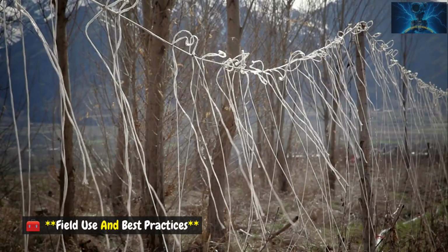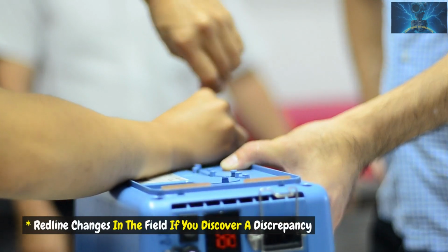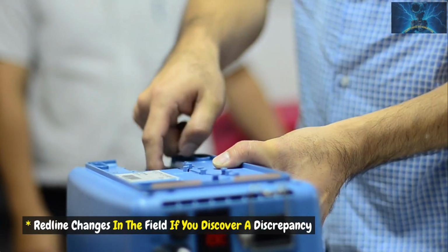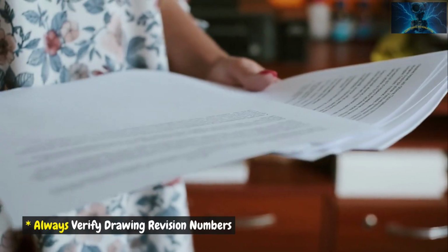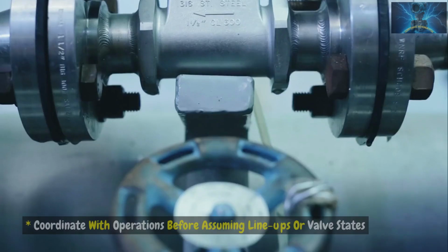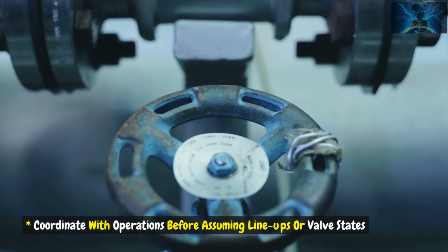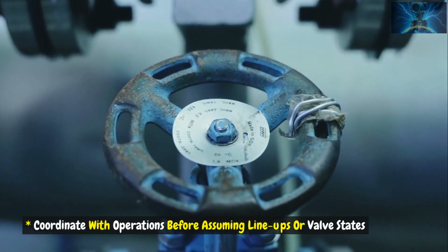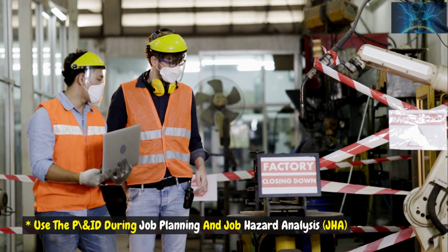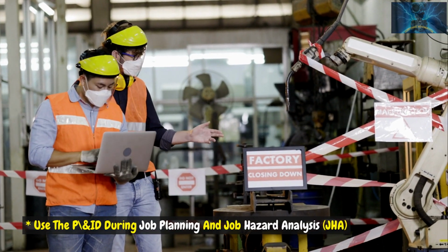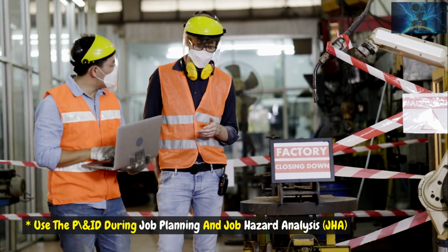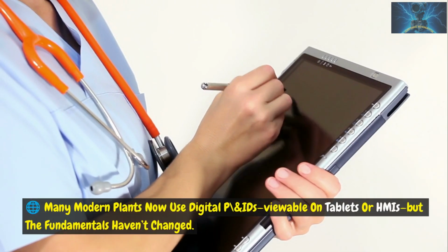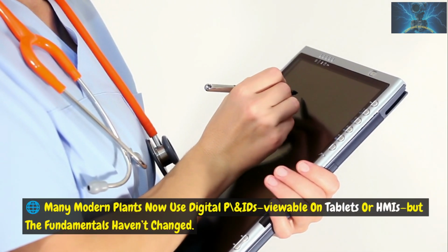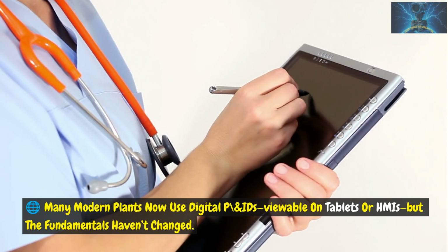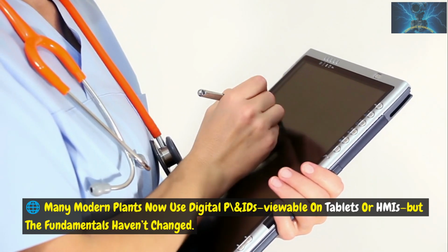Field use and best practices. Redline changes in the field if you discover a discrepancy. Always verify drawing revision numbers. Coordinate with operations before assuming lineups or valve states. Use the P&ID during job planning and job hazard analysis, JHA. Many modern plants now use digital P&IDs, viewable on tablets or HMIs, but the fundamentals haven't changed.